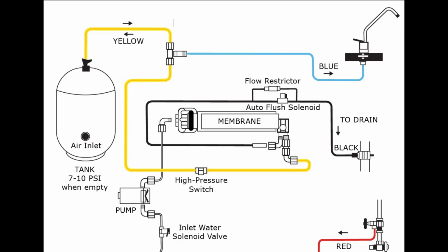such as the low pressure switch for the pump itself. In the case of the system we are using at this demonstration site, we pump up a pressure tank, which is about a 2.5 gallon tank, and it's in parallel with the outlet faucet. So the system will automatically fill up this container with water. The air bladder will compress up to match the pressure on the pump itself. When you open up the faucet, this water will come out. As it drops low enough, the automatic control switches will activate the pump again, refilling the bladder.